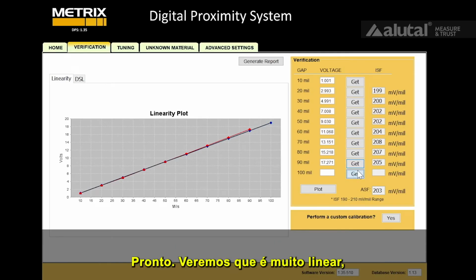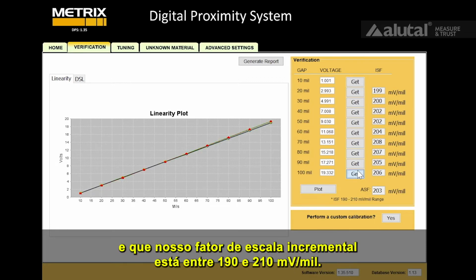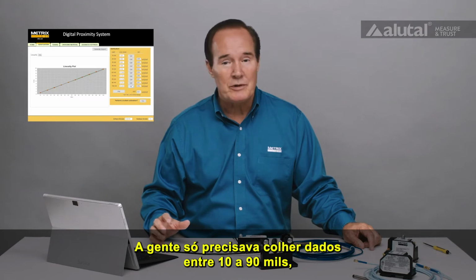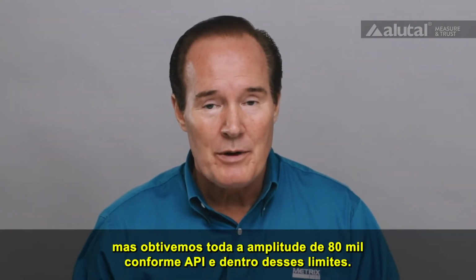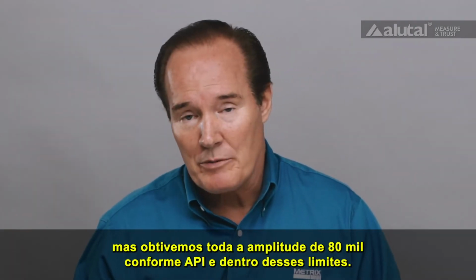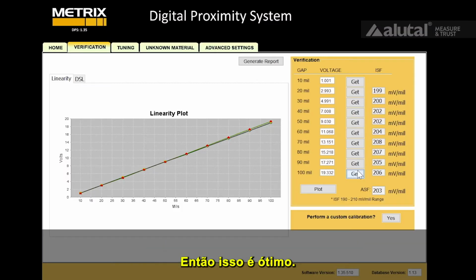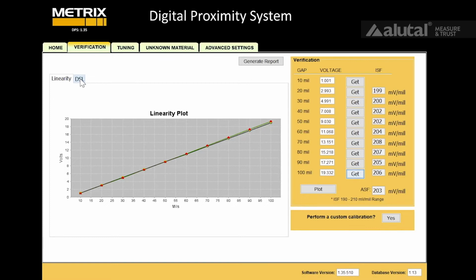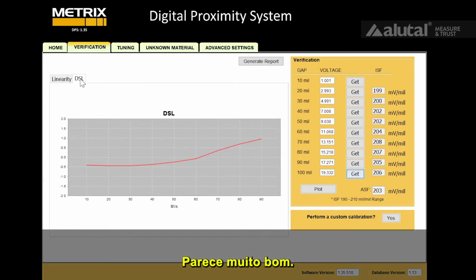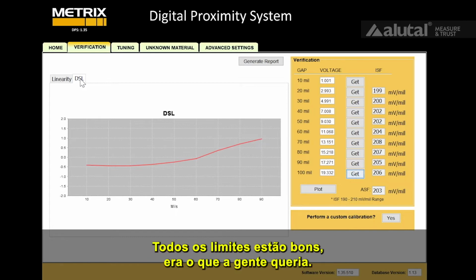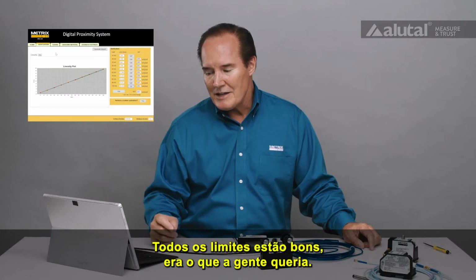When we take that, we'll see that it's very linear, and our incremental scale factor is between 190 and 210. Now it only had to do that between 10 and 90 mils, but we've got the full 80 mil API range within those limits, so that's very good. Let's take a look at deviation from straight line. That looks very good. It's between 1 and -1, and that's where we need it to be. So all the limits look good, and that's what we wanted.